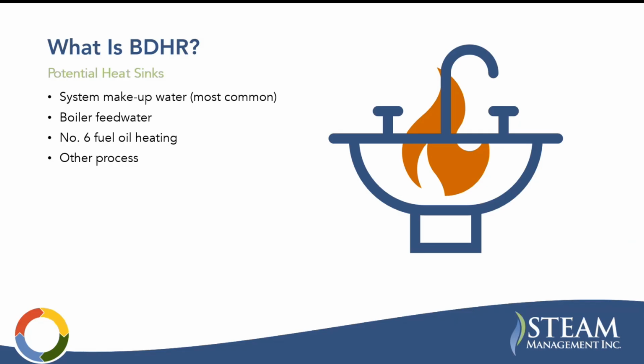What are the potential heat sinks? System makeup water, as I've mentioned multiple times, is the most common. You could also use the blowdown to heat boiler feed water. I've seen systems where they use it to heat their fuel oil. Fuel oil has to be kept warm in order to handle it and use it in the burners. It's getting a little bit scarcer to see boilers using number 6, but they still exist. And any other processes. This is a source of heat, and if you can find an applicable use for the heat, you can do that.